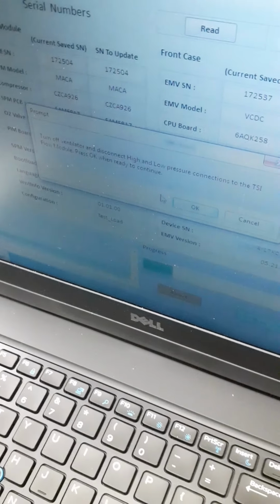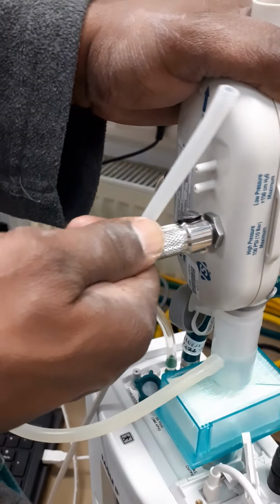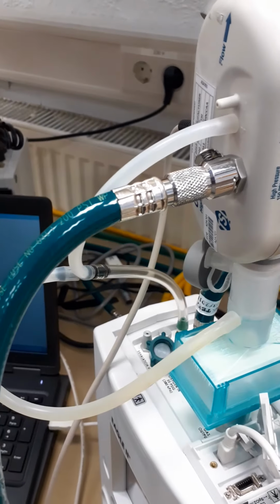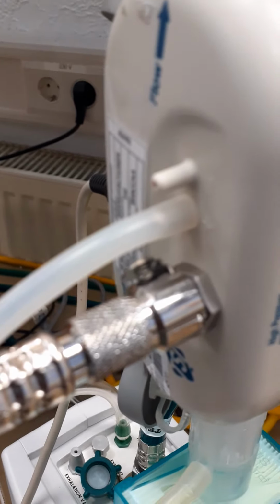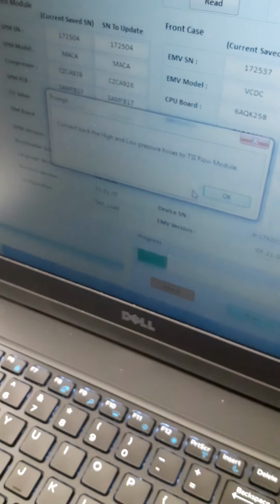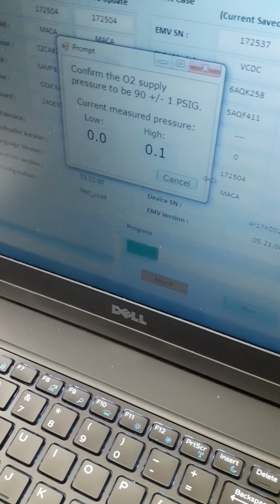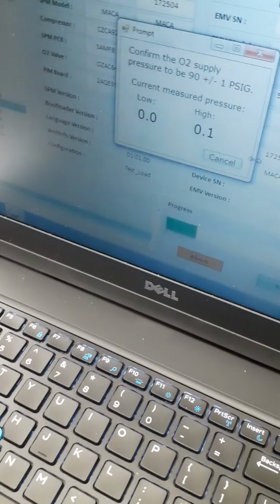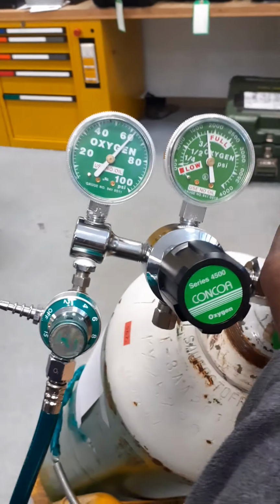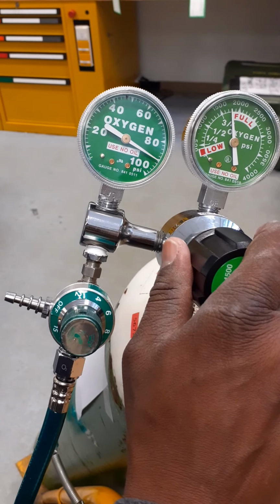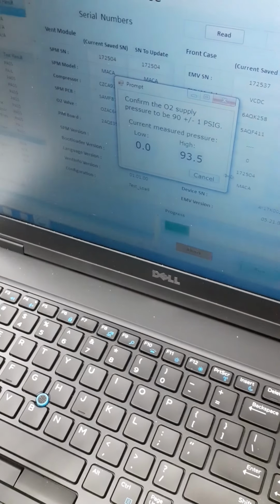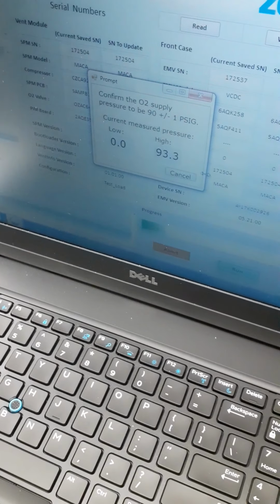In these tests, sometimes you'll find some of them that are sort of missing a final piece. What I find in some of them, you should put this back on, even though it doesn't tell you to, before you start the test, because the test starts immediately with no pressure on there, and some of them require you to keep it off. It all depends. Let me see if this is the one that I'm looking at. Okay, there it goes. It tells me to connect it back. It's looking for 90 PSI. Let's wait for it to stabilize. It's a little high. It's plus or minus 1 PSI that we're looking for.